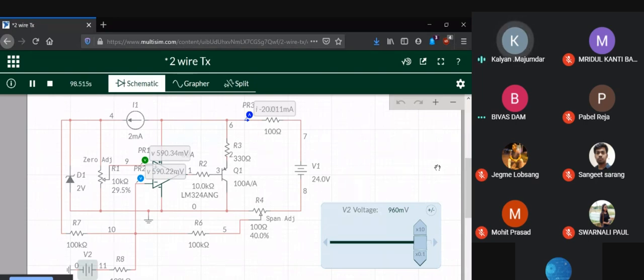That is what is expected, কারণ এখানে আমরা স্প্যান চেঞ্জ করেছি। সো মেজারমেন্ট স্প্যান আগে যেটা ছিল 0 থেকে 800, that has been redefined, has been altered to a new value of 0 থেকে 960 millivolts. কিন্তু আনফরচুনেটলি যেটা হয়েছিল, স্প্যান অ্যাডজাস্ট করতে গিয়ে জিরোটাও কেটে গেছিল, সো জিরোটাকে রিঅ্যাডজাস্ট করে আবার ওই 0 মিলিভোল্ট দিলে 4 মিলি অ্যাম্পিয়ার আসবে, সেটাকে রিসেট করতে হয়েছিল। So this is again as per what is predicted by your theoretical equation. So this is the simulation part of your circuit.